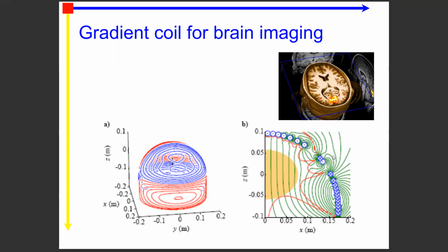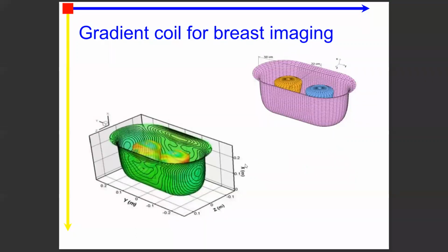They can quench, heat up, and the superconducting will stop, causing the helium to vent outside at high pressure, and that's not good. That's actually an accident, so we have to prevent that from happening by shielding this system with secondary windings.